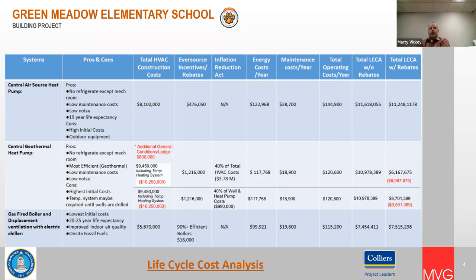The thought right now is that we'd be able to keep all the piping and infrastructure downstream in the building, just changing out the head-end equipment of the boiler room. Fin tube, for example, if it was originally sized for the lower water temp and you went higher, it's not a problem. Going backwards, you'd have a little less output at that point. So we just want to make sure that's covered.